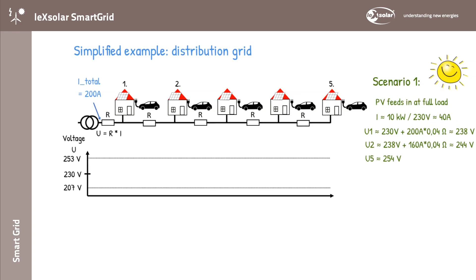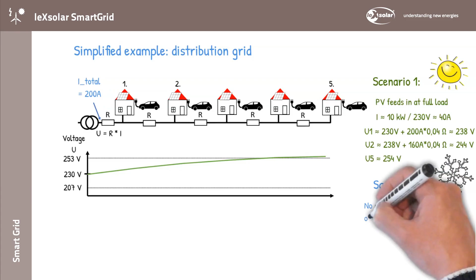In the second scenario, it is winter and there has been very little sunshine for days, so the storages are empty. In the evening, the families come home and all charge their electric car at full load, start cooking and thus arrive at a total consumption between 11 and 13 kilowatt, which corresponds to a current of 60 amps per house. Calculating the voltage again, we get 218 volts at the first house. At the end of the street at the fifth house, the resulting voltage is 194 volts, which is well below the 207 volt minimum.